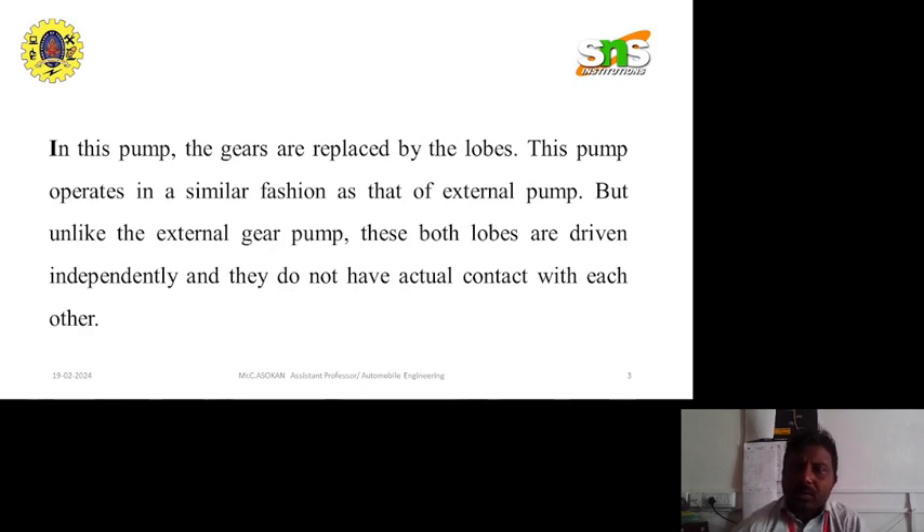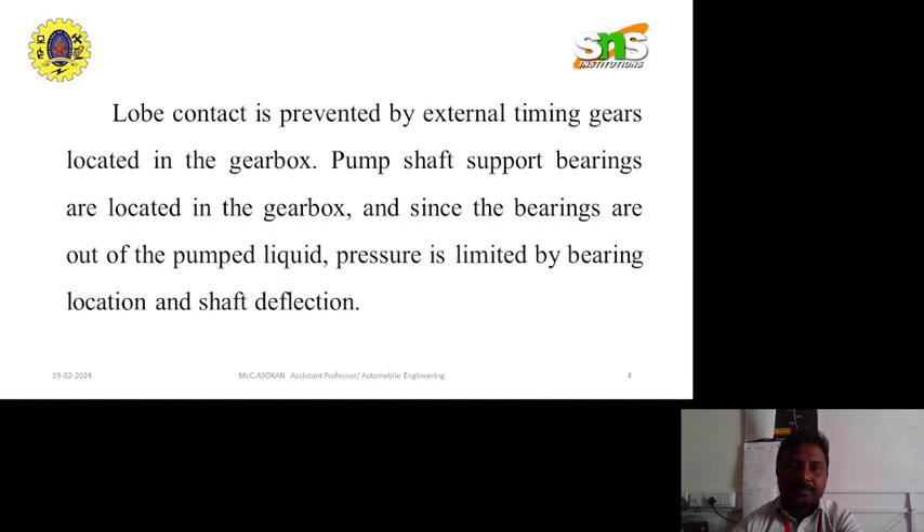The liquid flows into the cavity and is trapped by the lobes as they rotate. The liquid travels around the interior of the casing in the pocket between the lobe and the casing. It does not pass between the lobes. Finally, the meshing of the lobes forces liquid through the outlet port under pressure.